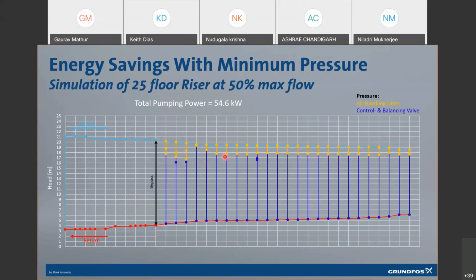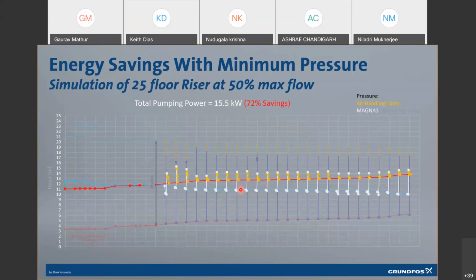However, the requirement is much lesser. So what do we do? We have to throttle and ensure that the flow is balanced in each equipment. And the large blue lines which you see are nothing but the killing of pressure. This visualization can be very well seen if you put the conventional system on the backdrop and see on the front what you have in a distributed pumping system.